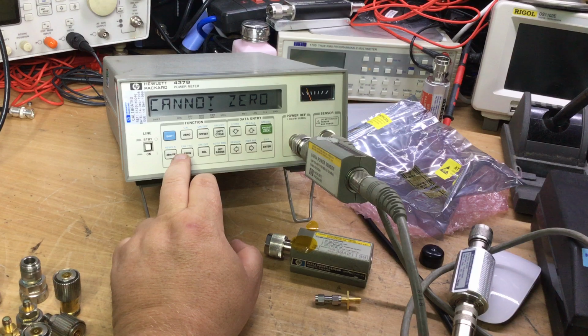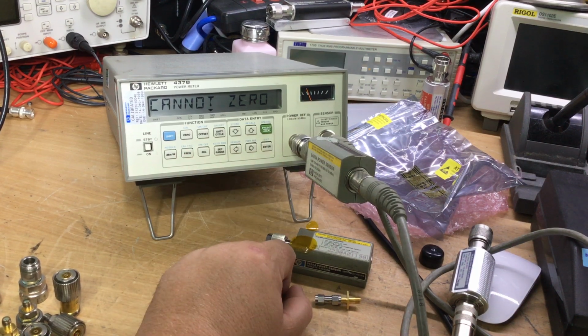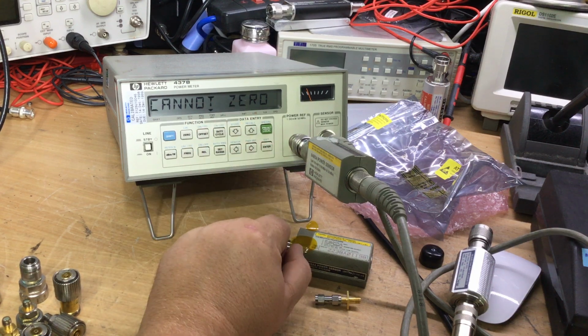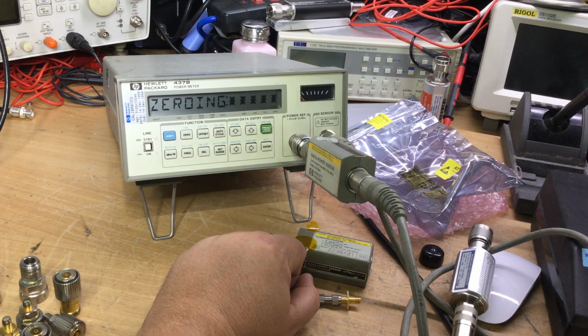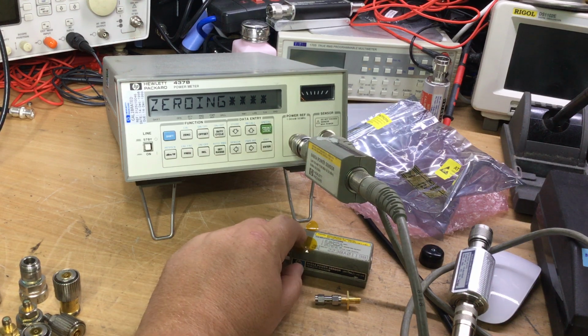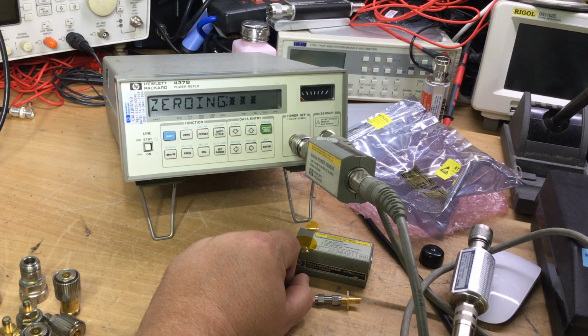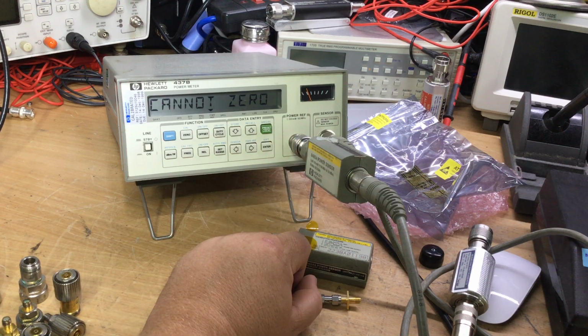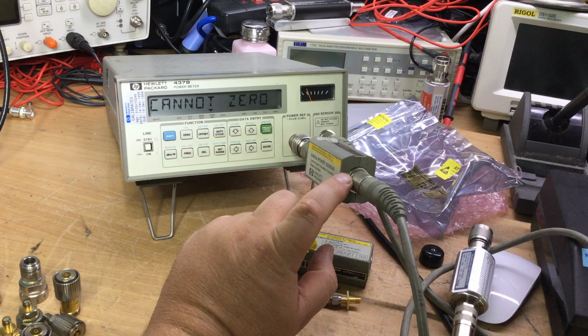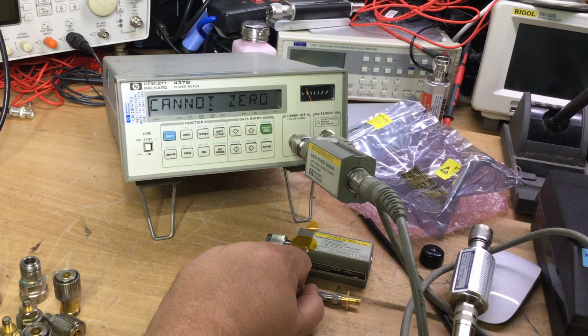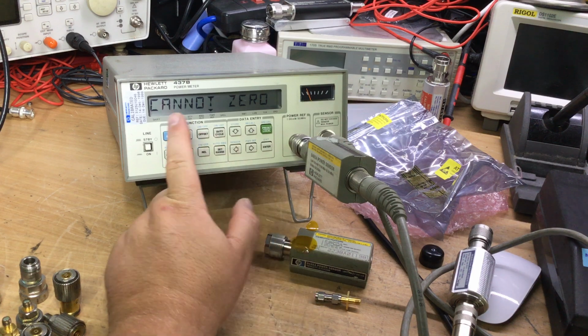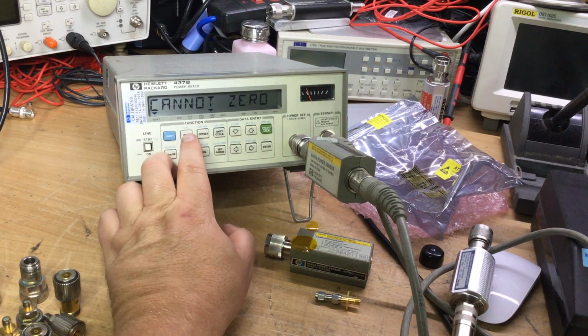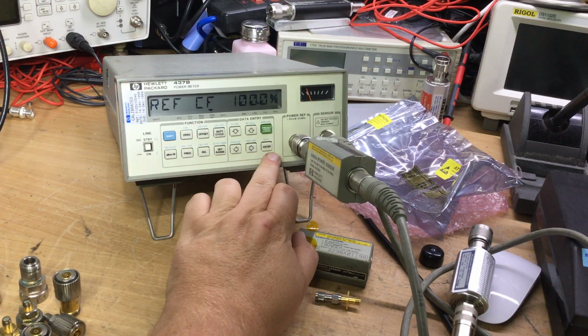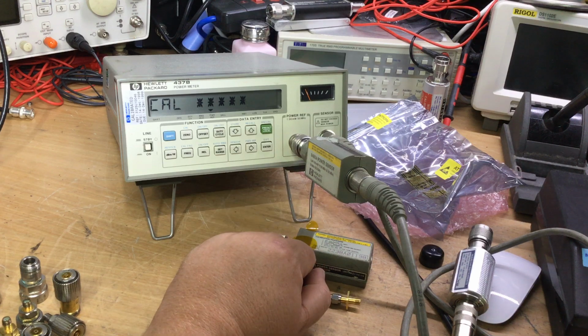Yeah, this sensor, it won't zero for some reason. I've just tried zeroing it because it came up on the display 0, but when you try zeroing it, it won't zero for some reason. Don't know why. Might be worth us taking it apart and having a look, just see if it's something simple, like the wiring loom for the plug there, perhaps. Which it says cannot zero though, which is strange. I wonder if it'll... calibration factor's 100% again on that one. So let's see whether it'll cal 0 dBm.